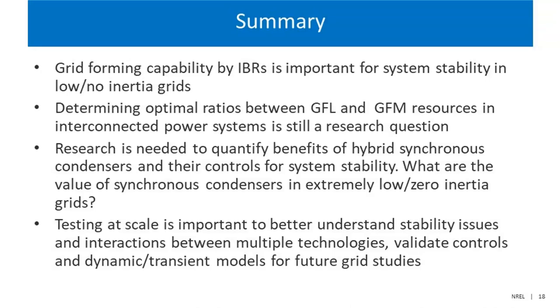So that particular case was one of the outcomes in the stability study we conducted for the Panhandle region. And we did some checks and tests. The participation in this case is two synchronous condensers against the rest of the ERCOT synchronous machines in the study case. And because the two synchronous condensers are embedded in more than 10 gigawatts of inverters, obviously the rest of the wind output also got affected associated with that 1.8 hertz. But in terms of participation in that case, it is particularly the synchronous condensers, which do not have a PSS, against the rest of the ERCOT synchronous machines.